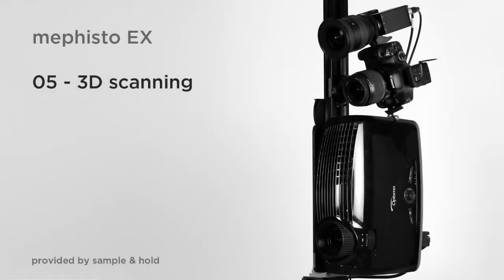05 3D Scanning. So the calibration is done. So long as you don't adjust the zoom or focus on any of the components or move them in relation to one another, you can use this calibration. We'd advise, though, if you leave the system for an extended period or aggressively move the unit, that you do a new geometric calibration to be on the safe side.